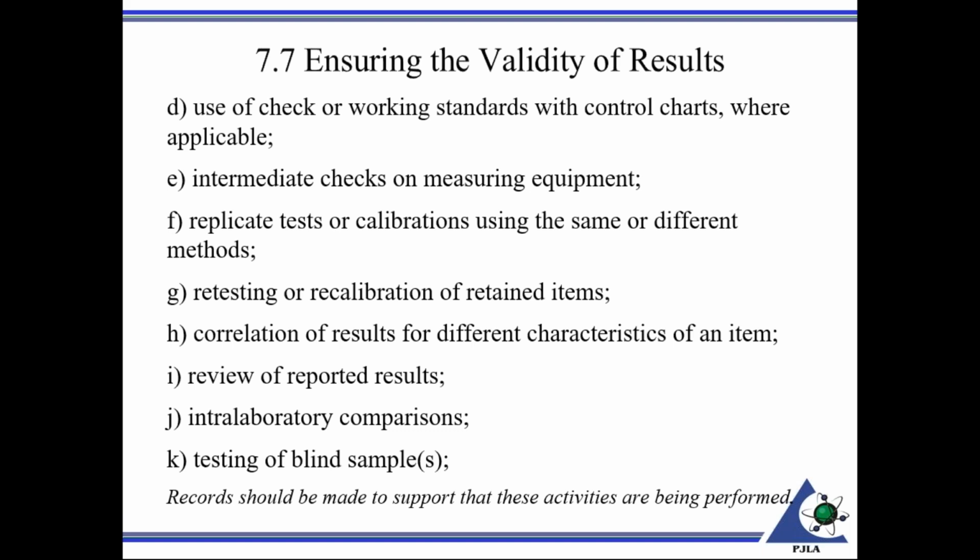K, testing of blind samples. So that could be, for instance, if you're a testing lab and you have samples and you retain those samples where they could be worked into the normal workflow. A technician can test that sample blindly, not knowing that it's already been through there, or perhaps even, I've actually implemented this in my brief career as a lab manager for a testing organization, where they could even be testing their own sample that they tested before and not even know it.